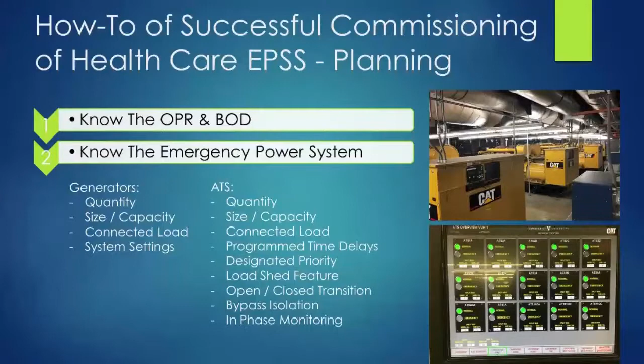So know the emergency power supply system sequence of operation. If it's a brand new facility, the engineer of record is going to help define this. You should be able to request, hey, I want the sequence of operation on how you intend the system to operate, or the vendor supplying the paralleling gear or the generator sets should be able to say, this is how my system operates. Then you can take that and help get the basis of your functional performance test written.